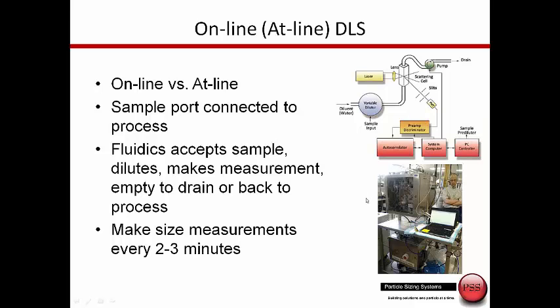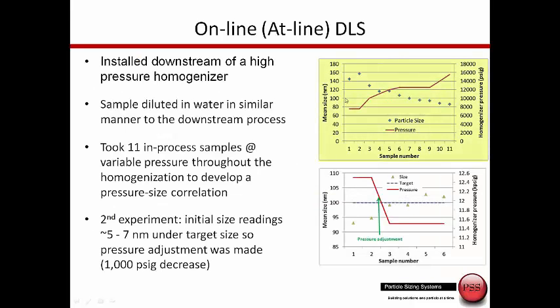This data is for nanoparticles used in drug delivery where each batch is very high value. The customer wants to make sure all samples are within size specification. This is the system installed at a biopharmaceutical plant in Cambridge, Massachusetts. The results show mean size in nanometers and homogenizer pressure. The system was placed downstream of the homogenizer. Eleven measurements were made. The customer wanted to understand the relationship between homogenizer pressure and generated particle size. As the pressure increases, the size distribution decreases.